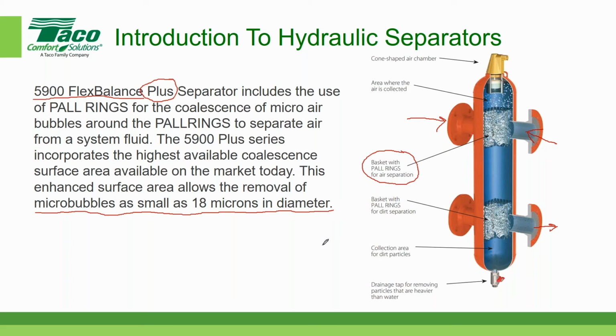So very tiny. The hydraulic separator, whenever we add the Pall Ring basket and the Pall Rings, it converts it into a combination hydraulic separator and an air and dirt separator. So if someone is considering a hydraulic separator for their system, they may want to consider this device because instead of buying two separate devices, a hydraulic separator and an air and dirt separator, they can buy one device that does both functions into one. So that is something to consider.